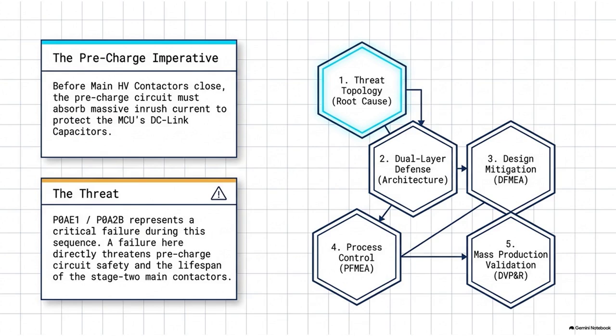So if the battery management system, the BMS, were to just blindly actuate the main high-voltage contactors and connect that 800-volt source directly to that uncharged capacitor, the instantaneous voltage differential would be catastrophic. Like opening the floodgates of a massive dam all at once. The rush of water would just obliterate the riverbanks. That's a great analogy. The inrush current wouldn't just be high, it would only be limited by the parasitic resistance of the bus bars and the internal resistance of the battery cells. We're talking thousands of amps instantly.